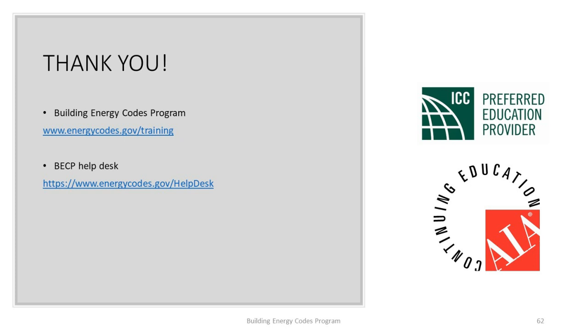One question was, will the new higher R values apply to remodels and re-roofs? And I think the answer to that is that the requirements for alterations that are in the IECC have not changed this cycle. So the new higher R values will be applicable in the same instances as the current requirements in IECC 2018. I think re-roofing is one of the exceptions where requirements don't apply, but other cases where the alteration requirements would require you to comply with the new construction requirements, those would still apply.